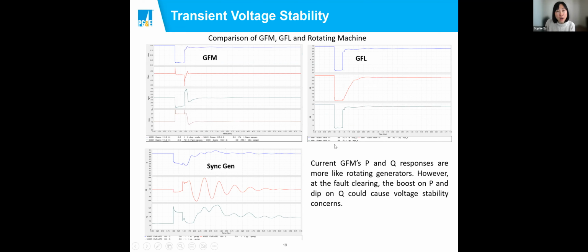And to better understand how this will change the grid by adopting grid forming inverter, I compared the same fault response from grid following inverter, and then on the bottom is the synchronous machine. And you can tell that the dynamic response from the grid forming inverter is more like a synchronous machine. For a synchronous machine, upon fault clearing, real power also goes up really quickly. That's because physically its kinetic energy was accumulating during the fault. And when the fault clears, it will go up and accelerate, and then oscillate, and hopefully we have enough inertia, and then it stabilizes in a post-contingency, post-transient state.